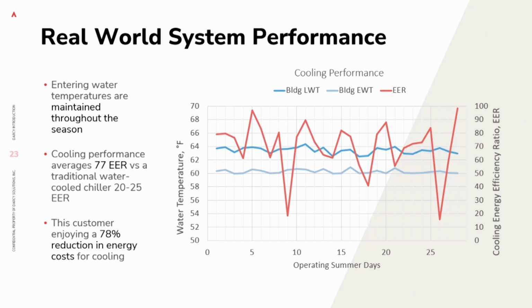This system feeds 64 degrees to the wells and returns 60 degrees, and we're getting EERs on average of 77 over the hottest 30 days of last summer. Compare that with a traditional water-cooled chiller at 20 to 25 EER, basically a 3x performance improvement. The other side benefit is that all those air handling units on the roof—24 of them—were removed, so now there's space for a solar system on the roof.